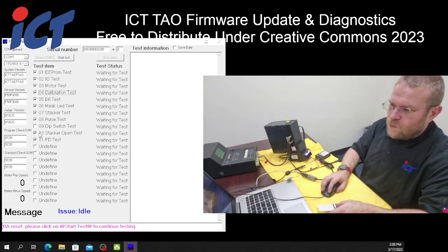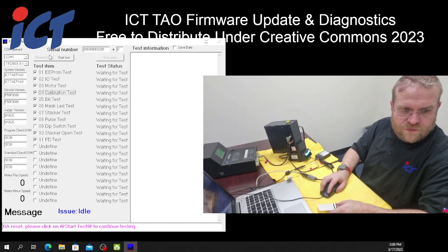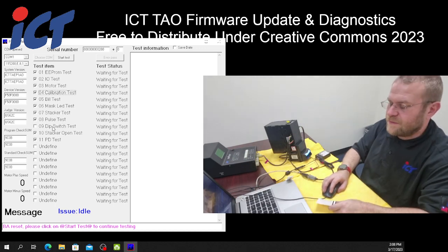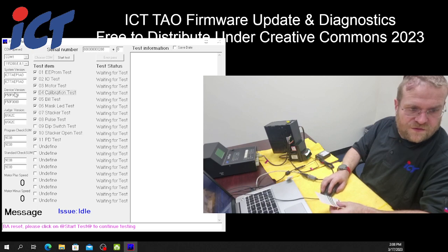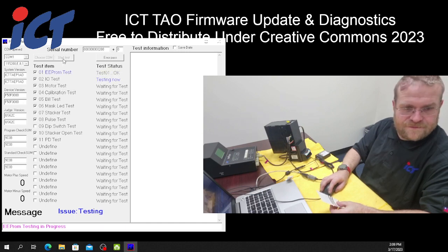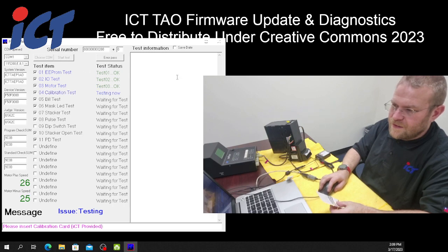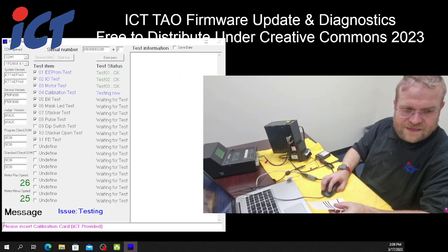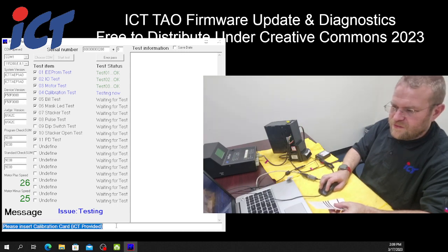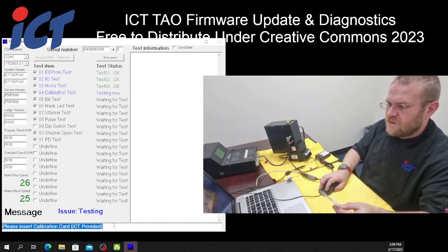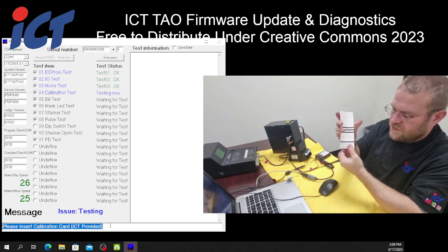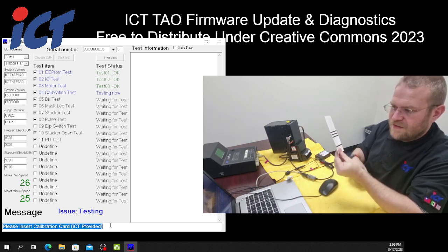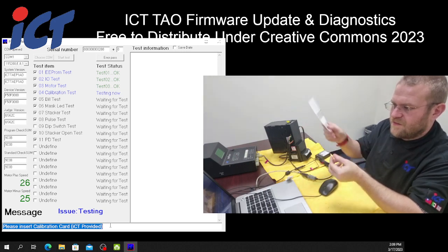So we'll go ahead and go through one of the diagnostics from start to finish, excepting the dip switch test like I mentioned. So with all of your fields on the left copied from the top to the bottom, go ahead and click Start Test. It will run through each of these, and once it needs something from you, it will tell you at the very bottom, user interaction required, please insert calibration card. So you would insert the calibration card by holding on to the little barcode at the bottom. That's going to be facing up as you feed.